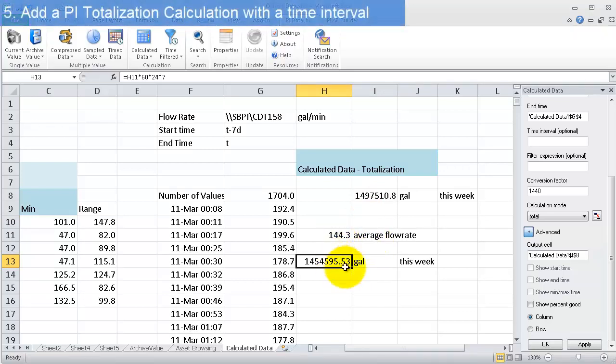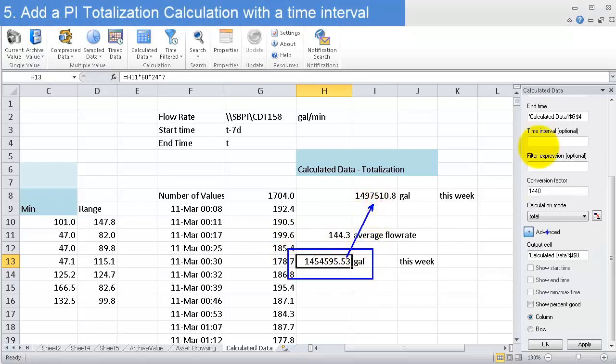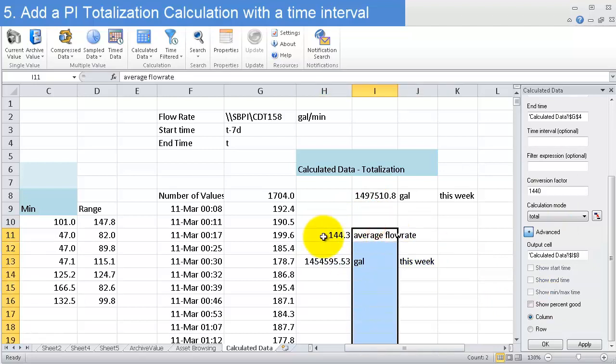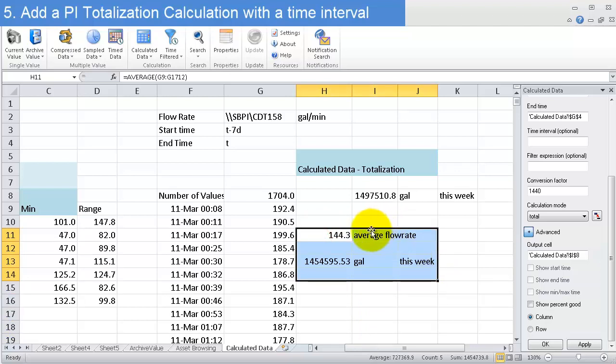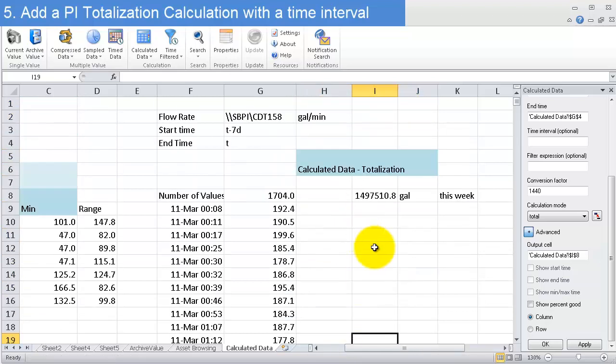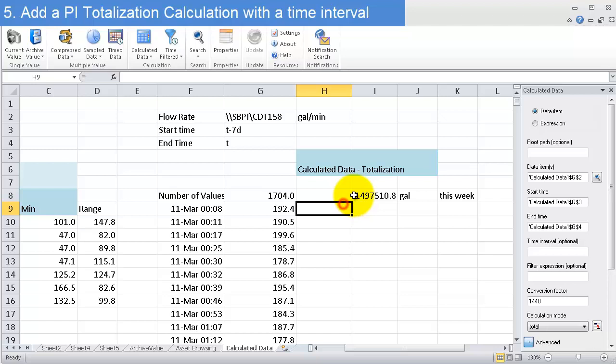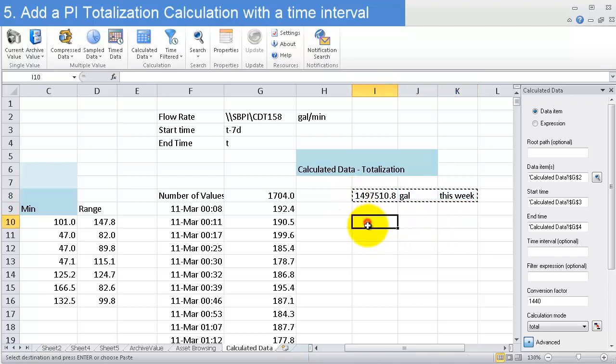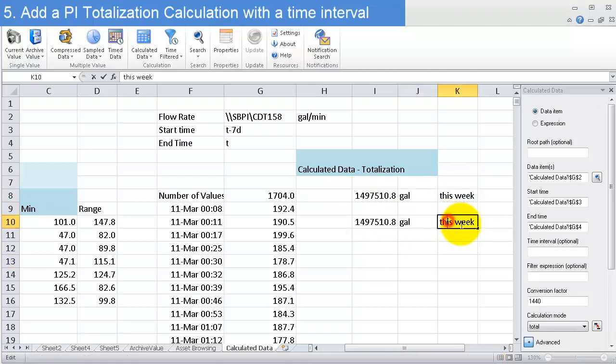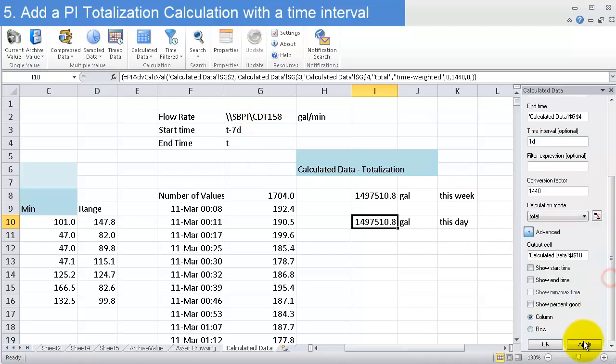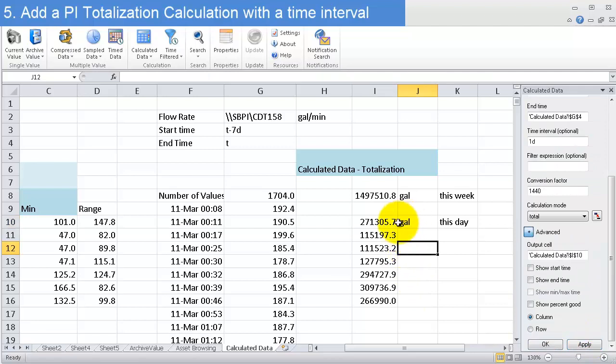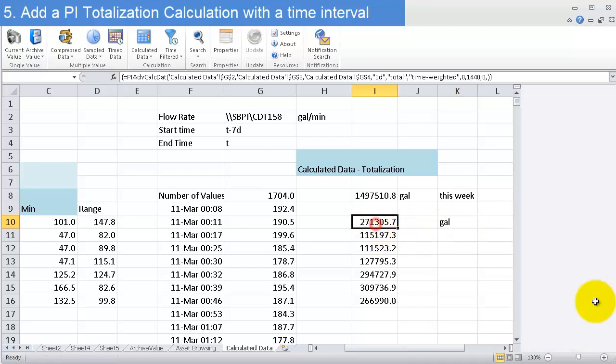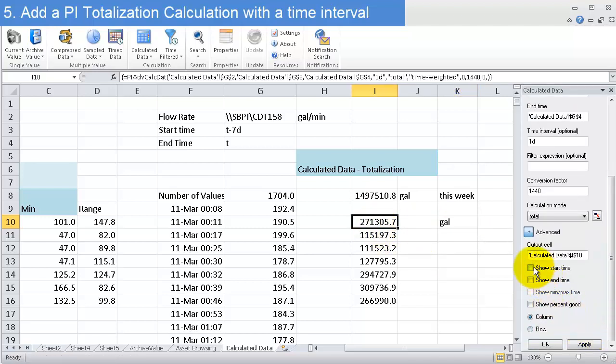Okay. Now, you might ask, well okay, it looks like I can just do this in Excel. So why would I want to do it with this calculated data function? Well, let me show you something that you can do that you can't quite do as easily with Excel. I'm just going to move this down. Maybe I want to know how many gallons did I produce each day this week. So I'll bring it down here, this day. All I need to do now is just change my time interval. So before it was over this whole week, now I just need to say one day, 1D. Click apply, and now I have daily values for each calculation.